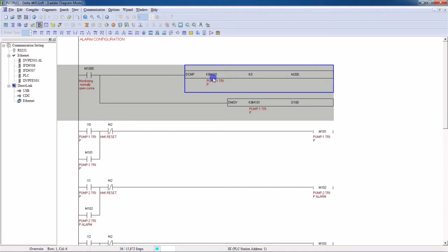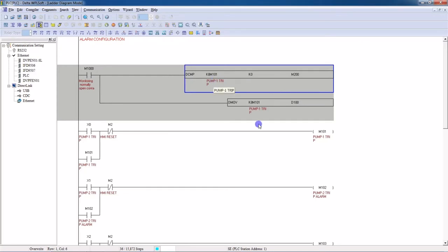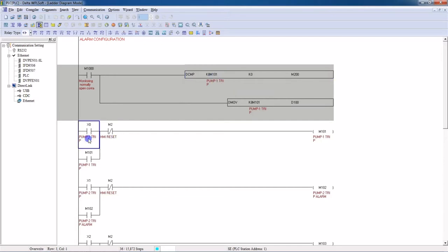There should always be spare bits from this register. If you have 20 alarms, then you should spare the next 20 registers for the alarms — do not use these registers anywhere else in the program. So your first alarm will start from M101.